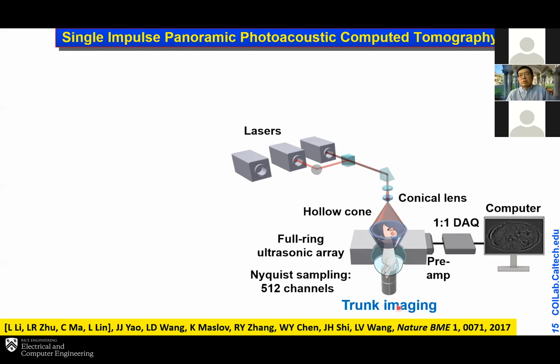And so we can configure the system for trunk imaging. You start with the laser, and you send the laser beam through a conical lens to produce a hollow cone beam. We generate the photoacoustic wave. And so you want to conserve every bit of laser energy. And that's where, for trunk imaging, the hollow cone beam is the optimal configuration. And we use a full ring ultrasonic transducer. Although I'm showing only half of the ring here, this full ring allows us to view the object from all possible angles. That gives us the best image quality.